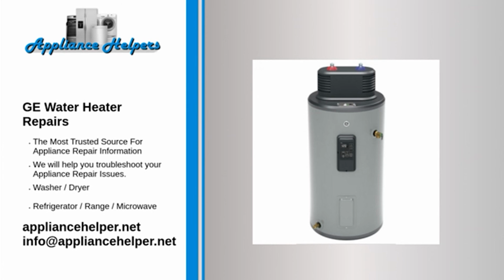Water heater not lighting. Some water heaters use an igniter to ignite the gas. If the igniter fails, the burner will not light. To determine if the igniter is defective, first make sure the igniter is getting voltage. If the igniter is getting voltage, but it doesn't glow, this indicates that the igniter is defective and should be replaced.